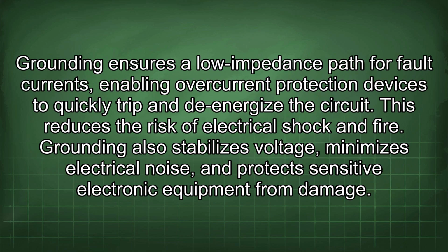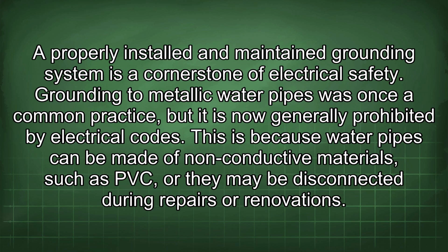Grounding ensures a low impedance path for fault currents, enabling overcurrent protection devices to quickly trip and de-energize the circuit. This reduces the risk of electrical shock and fire. Grounding also stabilizes voltage, minimizes electrical noise, and protects sensitive electronic equipment from damage. A properly installed and maintained grounding system is a cornerstone of electrical safety.